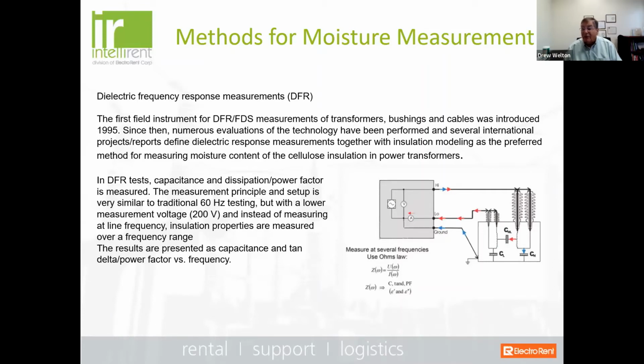It has to be done offline, of course, which also gives us quite a few challenges, especially with the heat that we're seeing this summer across North America. Nobody wants to take their large transformers offline. But unfortunately, if you're going to do good maintenance testing and you don't have a complete monitoring system on the transformer, this is going to be quite necessary.